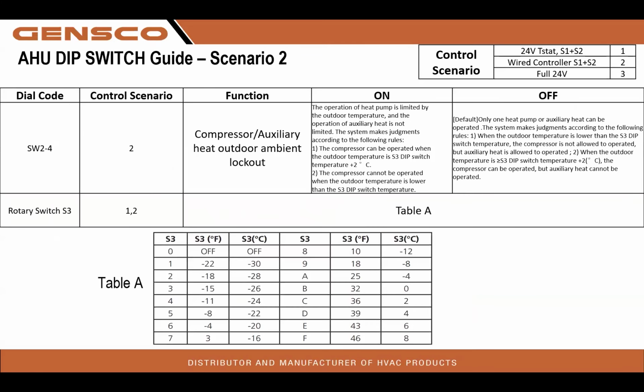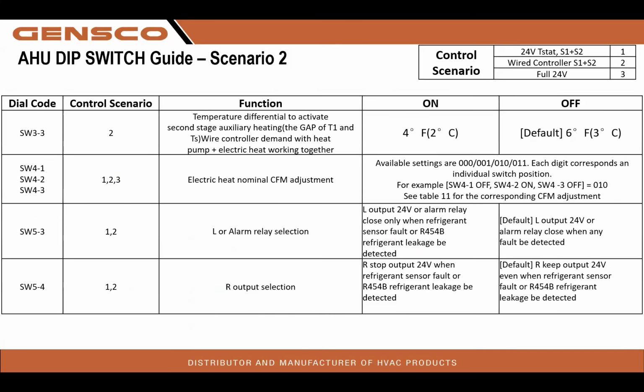Compressor and auxiliary heat outdoor ambient lockout. We can lock out the compressor at a certain temperature. I don't know why we would let this high-performing equipment run. More dip switch settings. It does seem like there's a lot of dip switch settings, but guys, at the end of the day, there is not. You're merely going to set dip switches as per how you want to set it up, but out of the gate, you really don't need to set any.